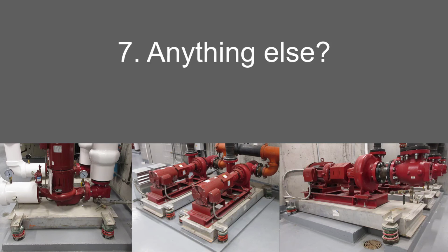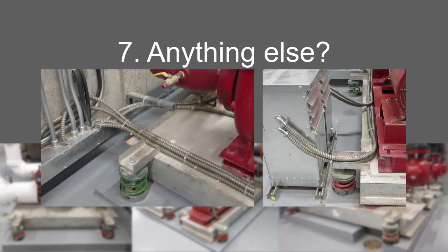Was there anything else? I wanted to mention that the flexible conduits were a good idea. There definitely should not be any rigid connection with the electrical connections. It would have been better, however, to provide more slack and even a full loop, where space permits, of flexible conduit between connection points, especially to transformers and wall-mounted distribution panels.